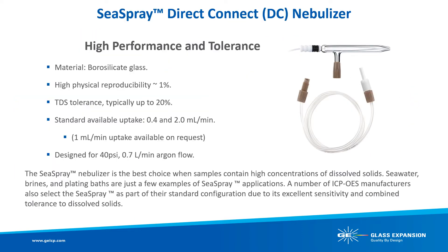A number of ICP manufacturers select the Sea Spray nebulizer as part of their standard configuration due to its excellent sensitivity and combined tolerance to dissolved solids. The unique polished tip provides a self-washing design offering freedom from clogging while nebulizing solutions upwards of 20% total dissolved solids, while providing excellent efficiency and sensitivity for trace level analyses. Sea water, brines, plating baths, and lithium salts are just a few examples of Sea Spray applications.